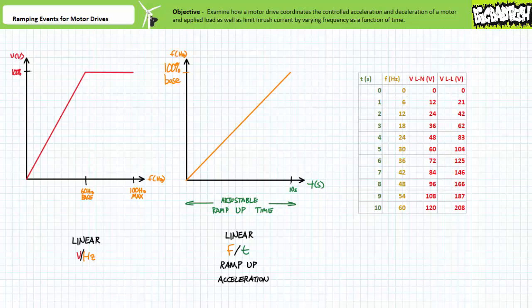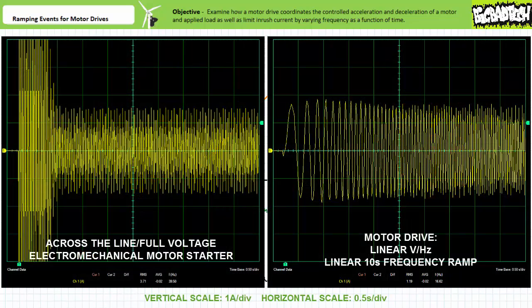This 10-second acceleration period is therefore characterized by both linearly increasing applied voltage and linearly increasing excitation frequency. One would anticipate the motor and driven load to be comparatively gently accelerated during this 10-second period, and inrush current substantially reduced in comparison to a full-voltage or across-the-line electromechanical motor starter that rudely jerks the motor and driven load to a start with a burst of full voltage at full excitation frequency. A graph of line current for an old-school electromechanical across-the-line full-voltage starter appears next to one making use of a motor drive where applied voltage and excitation frequency are both linearly ramped up during a 10-second acceleration period.